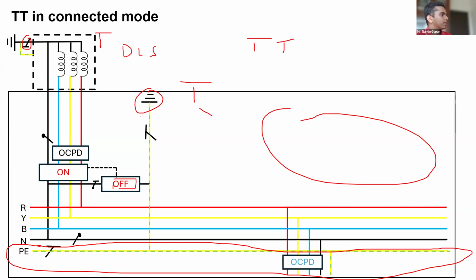So in this case, it is pretty clear. So this will be on. So this will be off, and this whole conductor won't be there. This whole conductor won't be there, and this will be a TT. So all the exposed and extraneous conductive parts are connected to an earth electrode, and the neutral of the transformer and the protective earth of the transformer are also connected to the earth electrode.